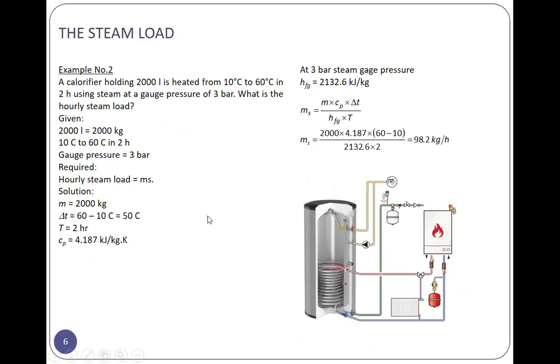So required for heating. A calorifier holding 2,000 liters is heated from 10C to 60C at constant temperature in 2 hours using steam at a gauge pressure of 3 bar. What is the hourly steam load? Since there is a specified 2 hours, you use this against the heat losses. It has insulation, so the computed value is lower. So use this one, because the 2 hours is specified.